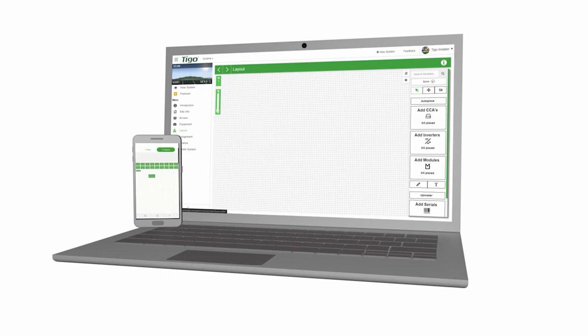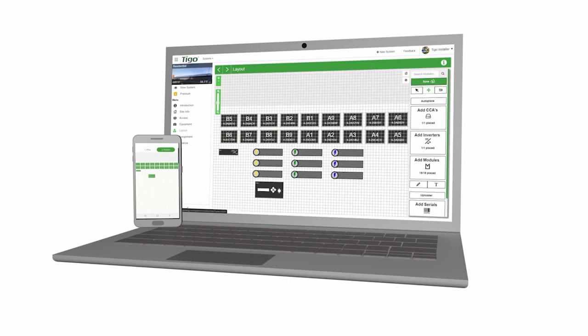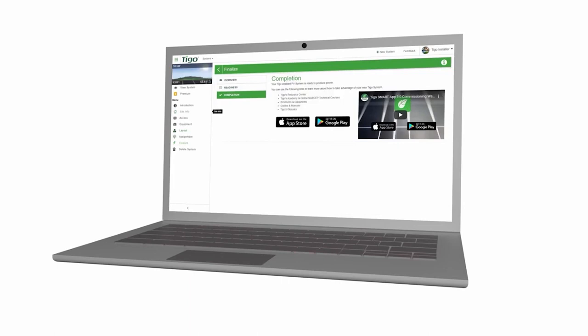In the design step, you can arrange your modules to match the physical installation. Place the modules individually or per string. Once all modules have been placed, enter the TS4 barcodes. This is the Tigo barcode located on the TS4 junction box or on the TS4-A add-on unit. You can also upload a CSV file using the available template located on the page within the Site Builder. In the confirmation step, review the information you entered and click the Finish button to transmit your CCA configuration file.